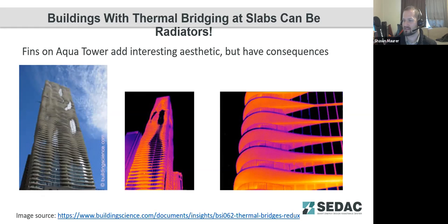So I wanted to touch back again on slabs because we see this a lot. Concrete slabs tend to puncture through the thermal envelope on a lot of buildings. So this is the Aqua Tower in Chicago. It's a very interesting aesthetic as you look up at it from the ground with the waving form of the different slabs coming through the envelope. Unfortunately, these slabs were not thermally broken from the interior. And you can see in the thermal images that this thing acts like a giant finned radiator, particularly in the cold weather. And in the summertime, it works in reverse. Heat can transfer through these slabs back into the building and add to the thermal loads.